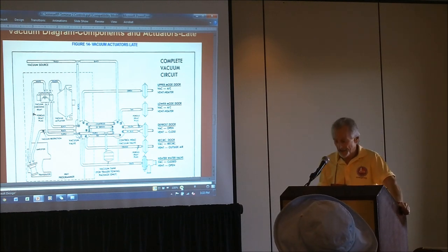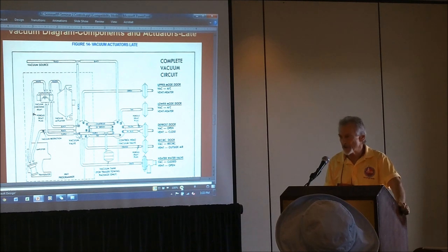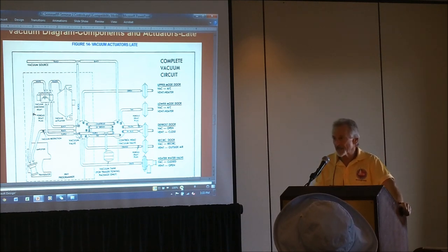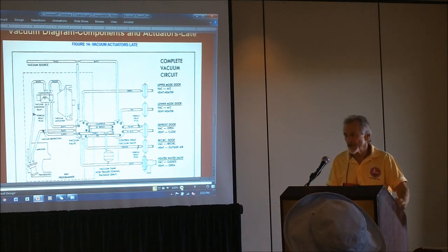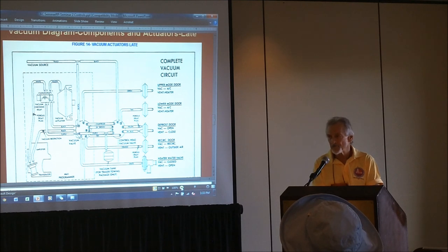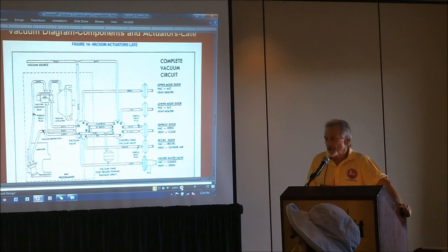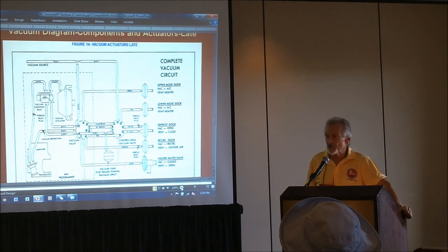414B, I've talked to refrigeration people who have actually used it to add in commercial refrigeration. They've actually added 414B to an existing R12 system while it's in operation. They've added it, supplemented. I personally have not done that, but they say you can. That was its intent. Again, for those commercial refrigeration systems, you're talking about a couple of pounds of refrigerant, just about the same as we've got in our car. So it is a legal, authorized, encouraged drop-in for 12. And again, I would assume that that's going to be around for a while.